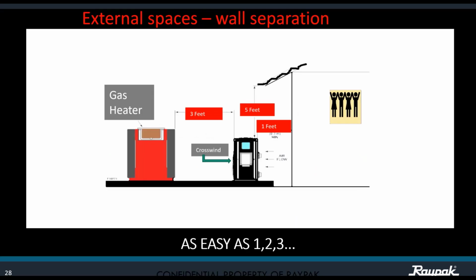Regarding spaces, especially if you are using a heat pump along with a gas heater, there might be a situation where you are trying to have a boost from the gas heater. Just make sure that you are 1 foot or 12 inches away from any wall and 5 feet on top of the unit. If you have a sloped roof like this, make sure that it's not going directly on top of the unit.